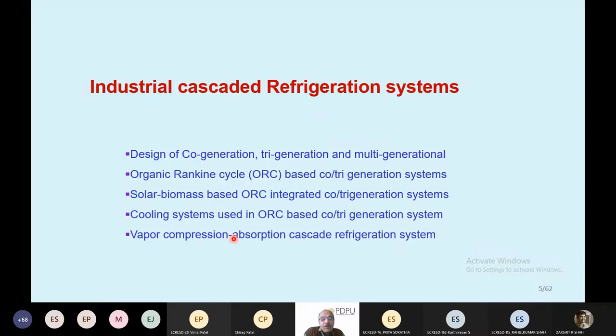The operating cost is high, but due to heavy systems, you cannot go below 10 kilowatt, or in industry normally 30 kilowatt is the minimum size available. So how can we incorporate the vapor compression and absorption system? That system is called a cascaded refrigeration system.